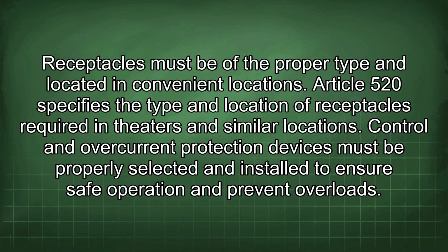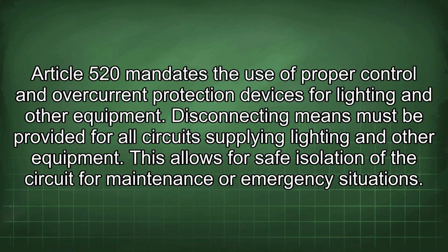Control and overcurrent protection devices must be properly selected and installed to ensure safe operation and prevent overloads. Article 520 mandates the use of proper control and overcurrent protection devices for lighting and other equipment. Disconnecting means must be provided for all circuits supplying lighting and other equipment. This allows for safe isolation of the circuit for maintenance or emergency situations.